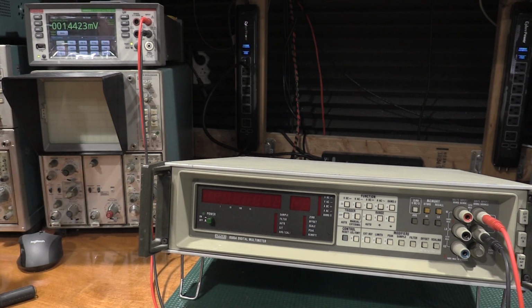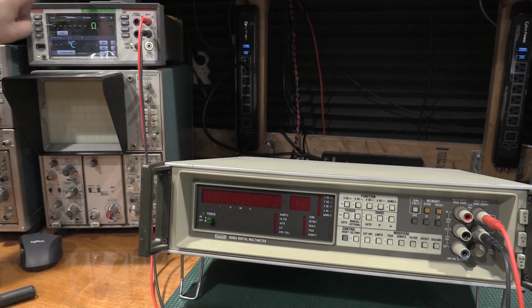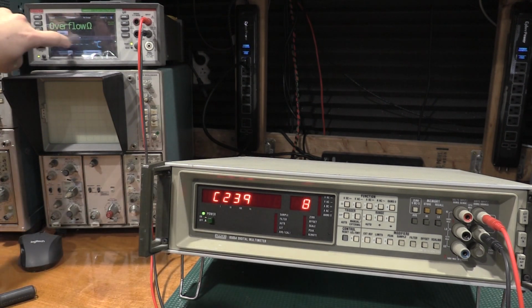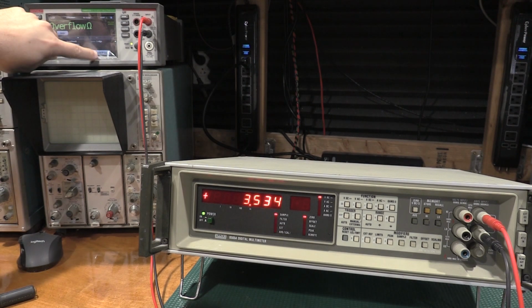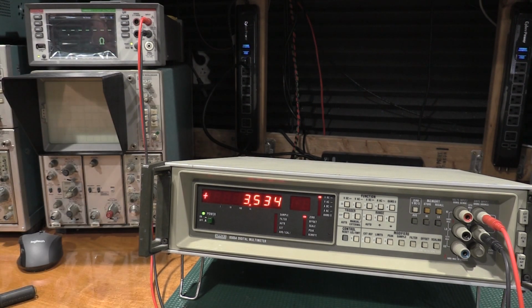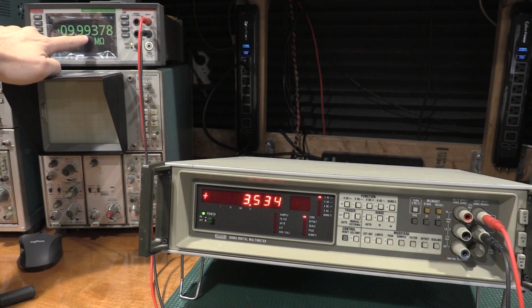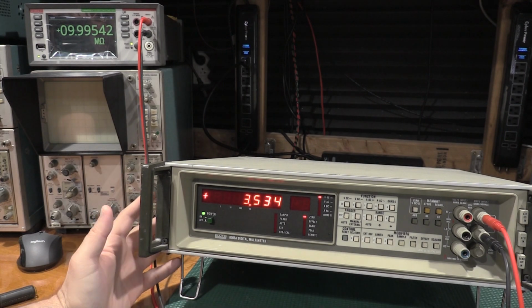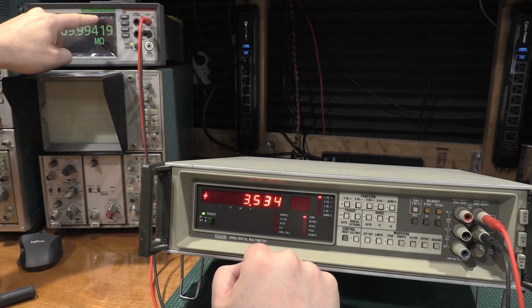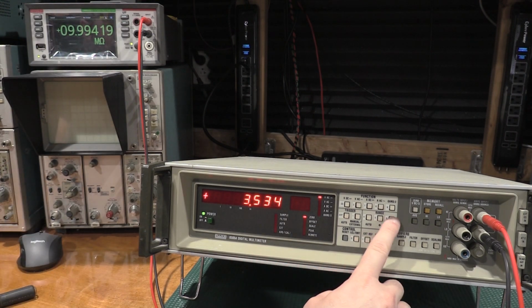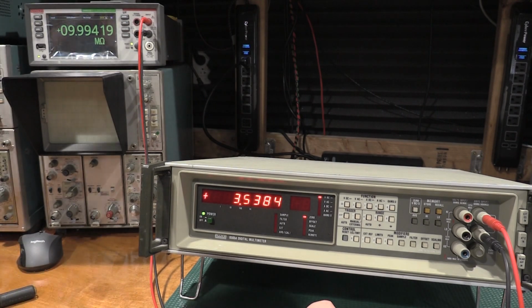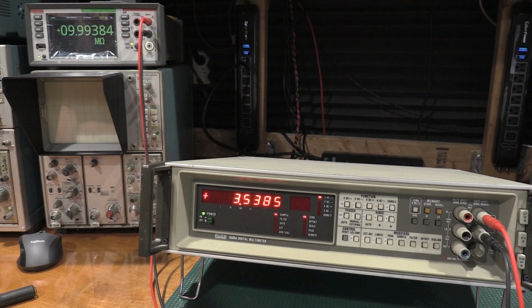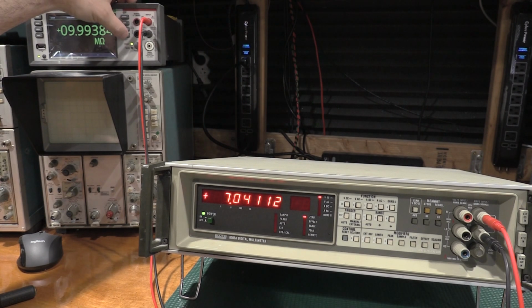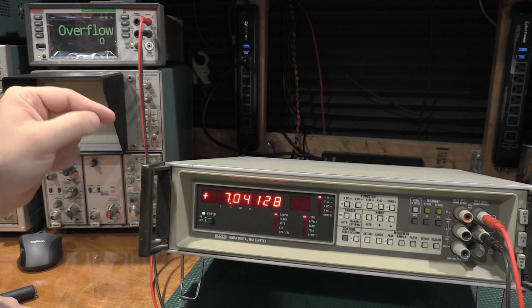So what we need to do is, I've had the 6500 warming up for a while, so it's ready to go. We'll kick this over to resistance measurements. Turn this on. And we have 99.99 megohms. So this is actually a very good candidate for using the high voltage probe. Actually, let me detrigger this so I know. Manual triggering mode. Change the range. Trigger the measurement. This one may actually be a very good candidate for my high voltage probe. I may need to switch meters. And that's actually what I wanted to show.